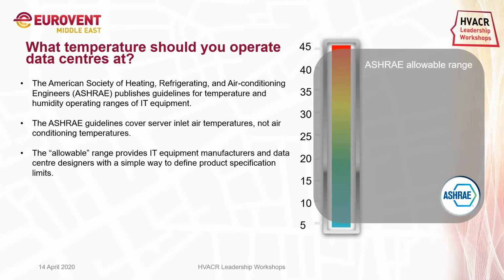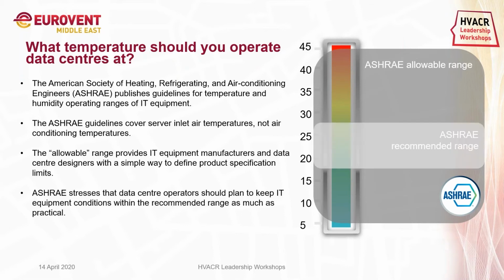Allowable range provides IT equipment manufacturers and data center designers with a simple way to define product specification limits. So, gathering the information from IT equipment manufacturers and the designers, they have plotted an allowable range of 5 to 45 degrees Celsius that the IT equipment can endure. Now, ASHRAE is stressing that data center operators should plan to keep IT equipment condition within the recommended range, which is from 18 to 27 degrees Celsius.